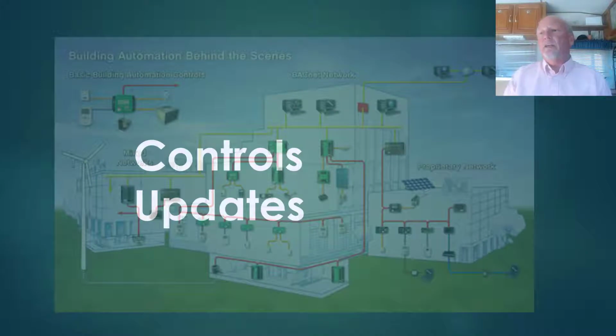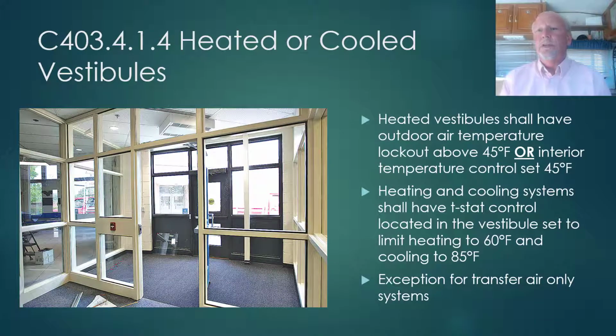Control updates. Now, we're not going to cover all of the control requirements of the Washington State Energy Code, but I've picked out a few updates that I think you may be interested in. The first one is vestibules. Vestibules are now required in the code for certain building types over certain floor areas, for main entrances in buildings over a certain size, and so we're seeing more vestibules installed in buildings. It is common to provide some kind of space conditioning in the vestibule to temper it on cold days as a transition space between outside and inside.